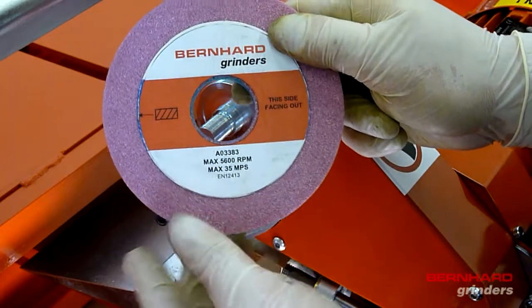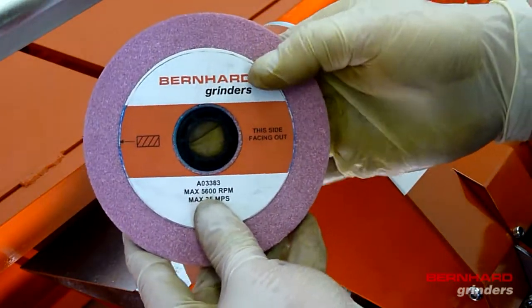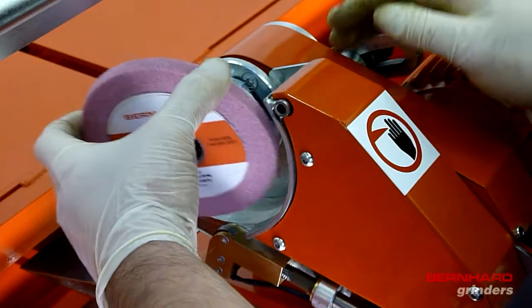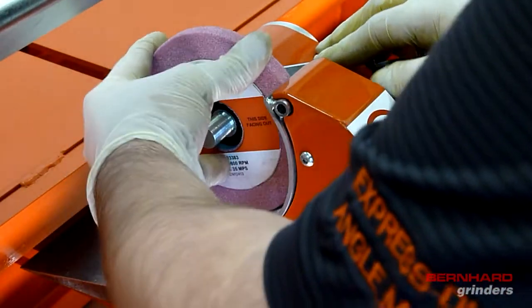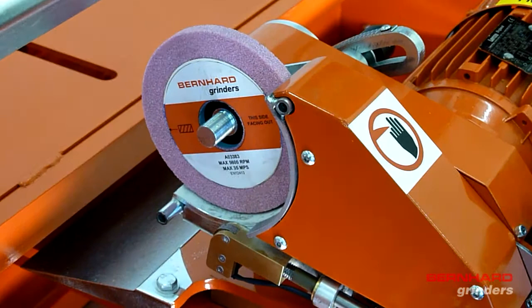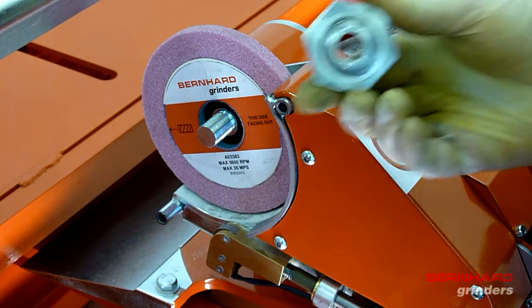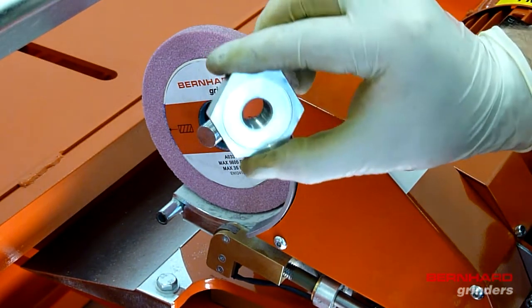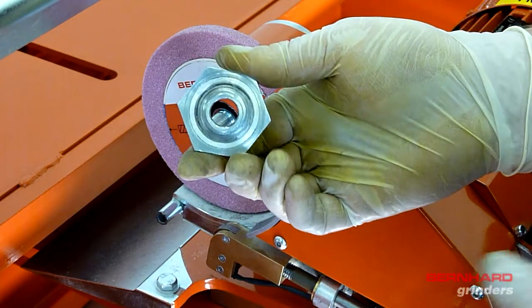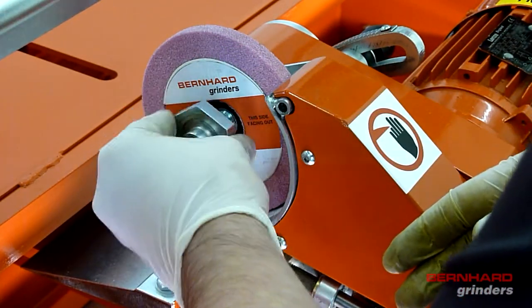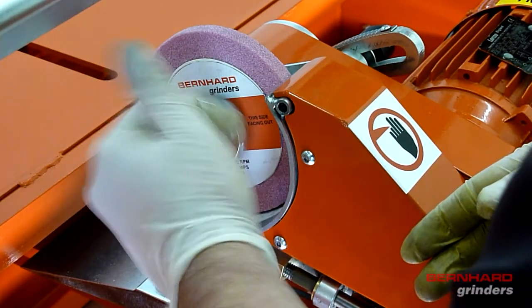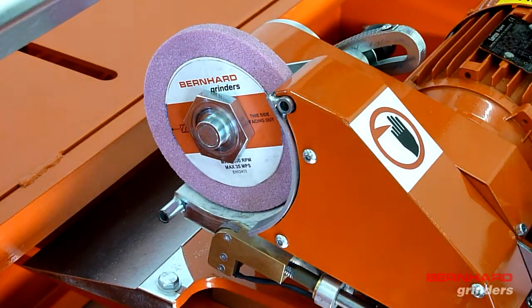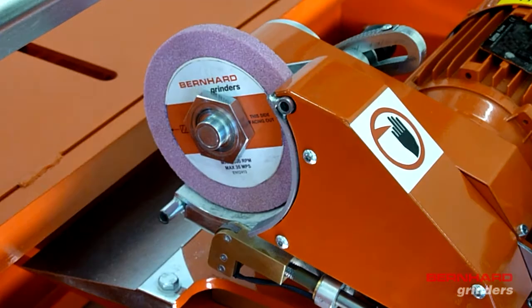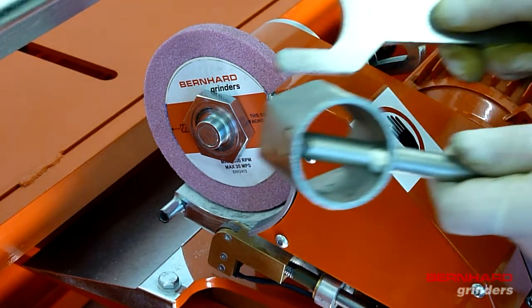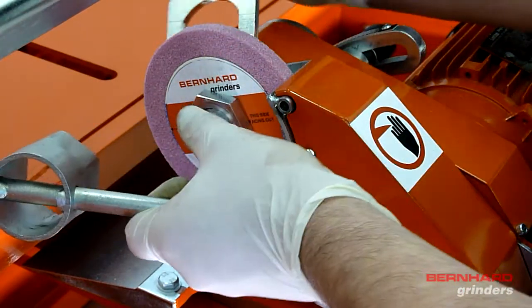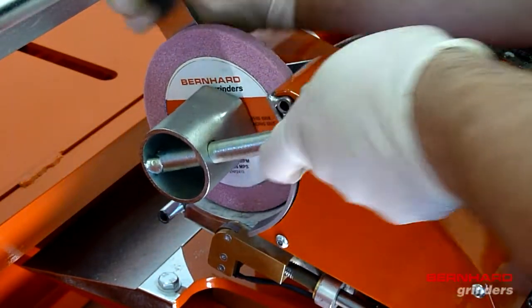When the correct side of the stone has been selected, fit the plastic spacer into the centre of the stone. The stone will now fit snugly onto the stone shaft. The stone is secured using a nut. For the relief stone, the shoulder of the nut should be facing outwards, away from the stone. Tighten the nut using the supplied box wrench and locking spanner. Tighten the nut in a clockwise direction.